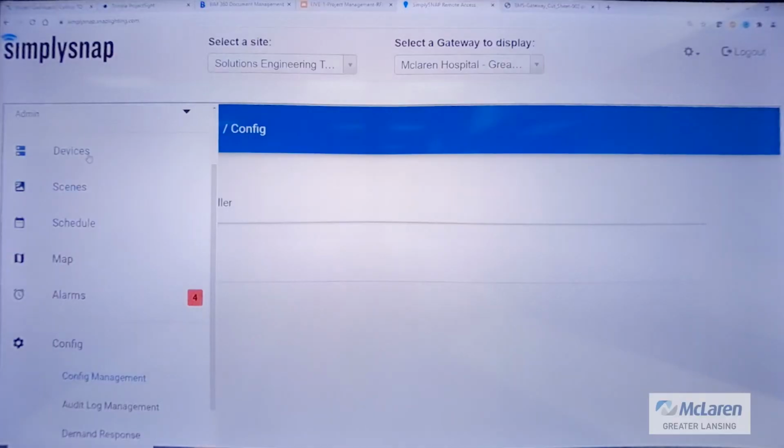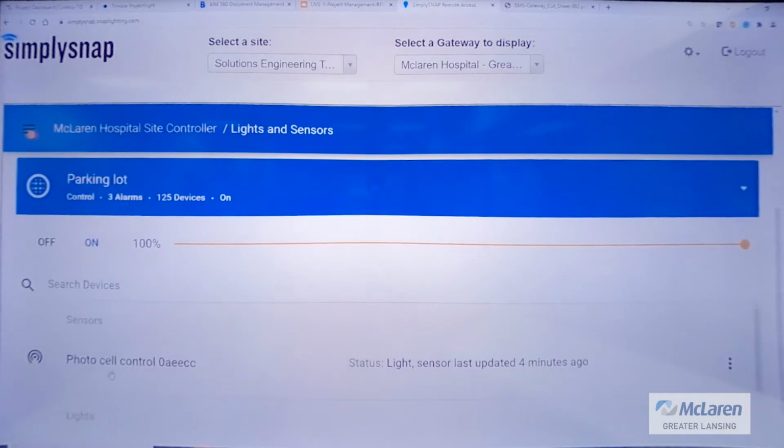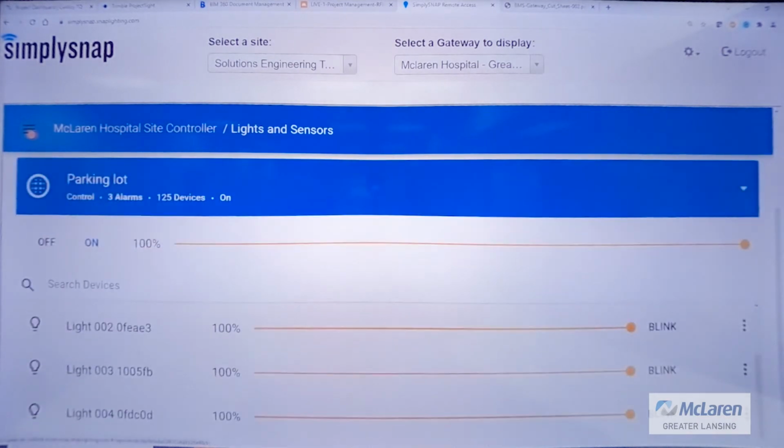Now, if the light was on in the other scenario, but we have lost communication with the controller, more than likely that's just a controller issue, because you know for sure the power is getting to the light because you see it visually lit. And at that point, the only issue is just trying to turn the light on and off. That's probably just a controller. You can look visually at, like I said, the power data in the light, and that sometimes will help you get an indication of what's going on.